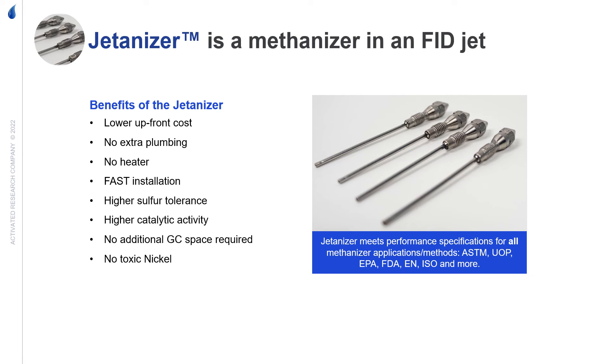When looking for a methanizer, the Jetanizer has the lowest upfront cost. No extra plumbing is required, which makes the installation as simple as changing out an FID jet. The catalyst has higher tolerance to sulfur and has a higher catalytic activity.